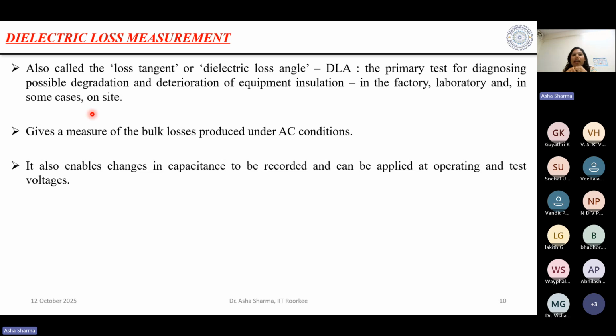This is a primary test for diagnosing possible degradation, meaning if R is very low, we say the material has degraded or deteriorated. This dielectric loss measurement can be done in the factory, in the laboratory, or on-site for condition monitoring. It gives a measure of the bulk losses produced under AC conditions, and these losses are something we don't want.